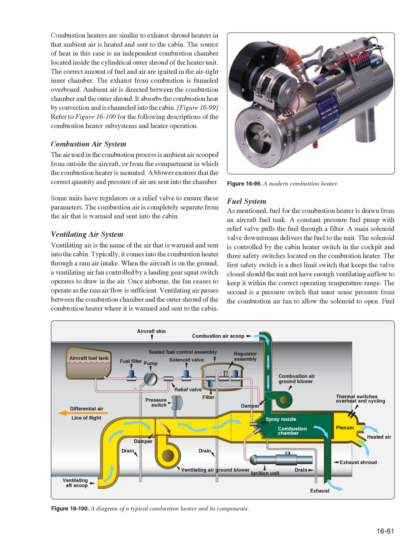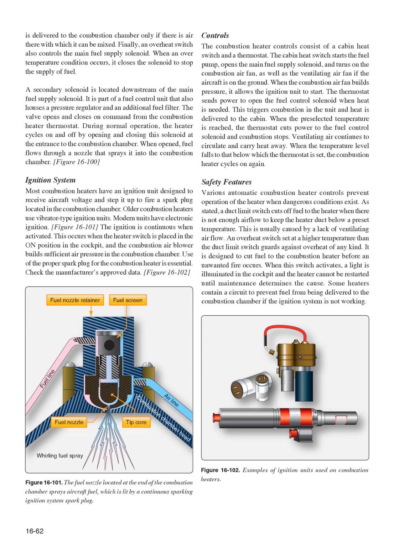The solenoid is controlled by the cabin heater switch in the cockpit and 3 safety switches located on the combustion heater. The first safety switch is a duct limit switch that keeps the valve closed should the unit not have enough ventilating airflow to keep it within the correct operating temperature range. The second is a pressure switch that must sense pressure from the combustion air fan to allow the solenoid to open. Fuel is delivered to the combustion chamber only if there is air there with which it can be mixed. Finally, an overheat switch also controls the main fuel supply solenoid. When an over-temperature condition occurs, it closes the solenoid to stop the supply of fuel.